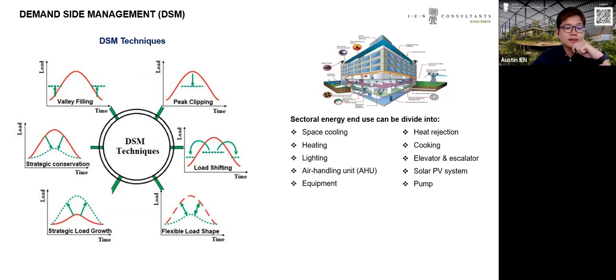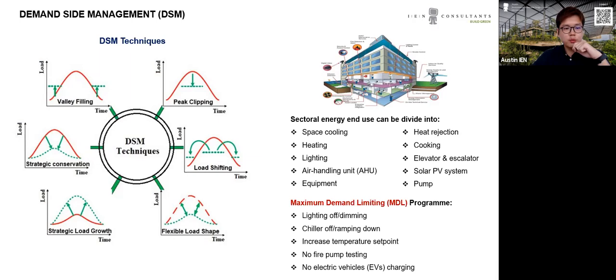Maximum demand is the highest level of electrical demand monitored for a particular period, usually a month. TNB needs to cater to this peak load whenever required by the customer, so customers are encouraged to control their electricity demand during the daytime peak hours. With BMS, we will be able to implement what we call the MDL program, or maximum demand limiting program.